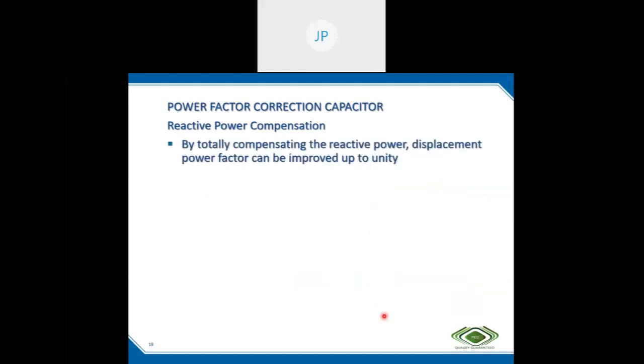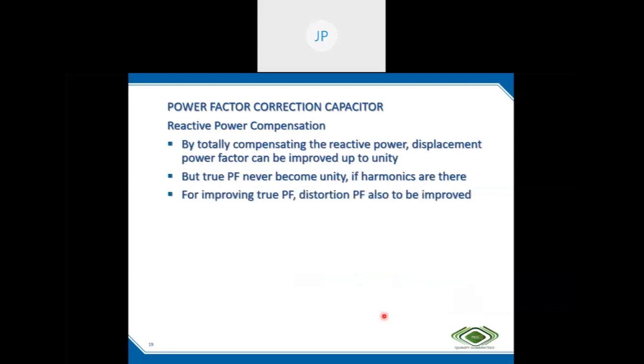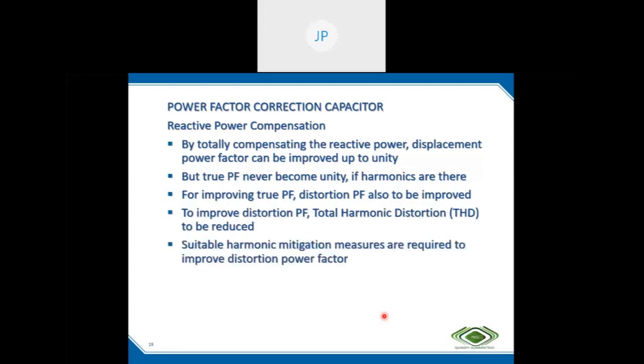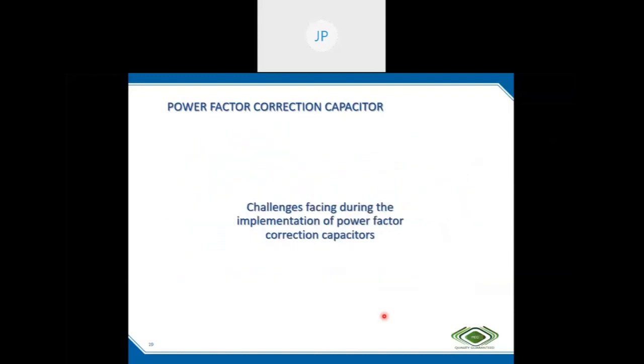So by totally compensating the reactive power, the displacement power factor can be improved up to unity. But the true power factor never becomes unity if harmonics are there. For improving the true power factor, the distortion power factor also has to be improved. Distortion power factor can be improved only by reducing the THD, the harmonic distortion. For that, we have to use some harmonic mitigation measures. That is, to improve the true power factor, both reactive power and THD have to be reduced.